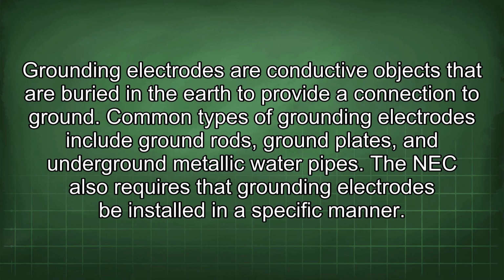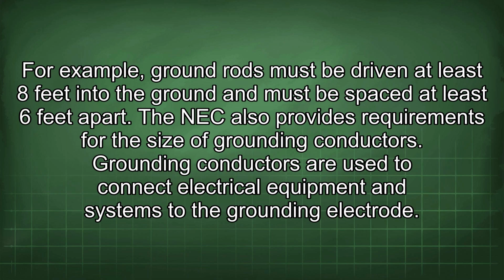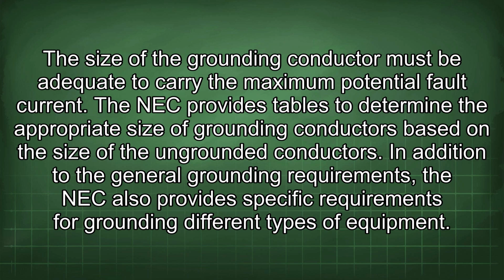The NEC also requires that grounding electrodes be installed in a specific manner. For example, ground rods must be driven at least 8 feet into the ground and must be spaced at least 6 feet apart. The NEC also provides requirements for the size of grounding conductors. Grounding conductors are used to connect electrical equipment and systems to the grounding electrode. The size of the grounding conductor must be adequate to carry the maximum potential fault current. The NEC provides tables to determine the appropriate size of grounding conductors based on the size of the ungrounded conductors.